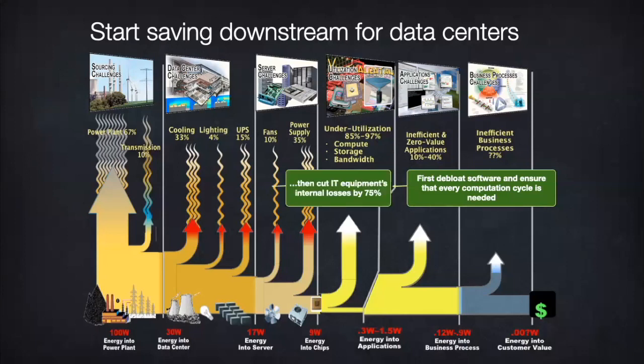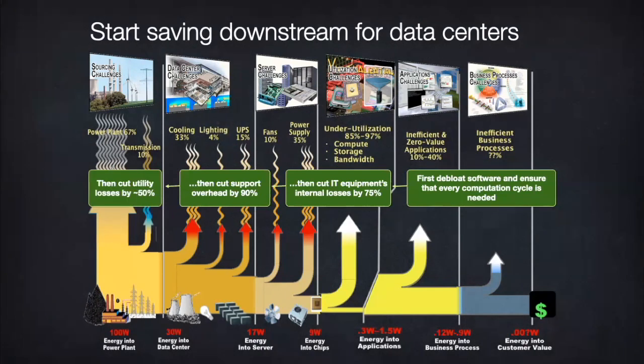Then at least quadruple the server efficiency, now even more, and the servers will need far less cooling and power supply, both of which can be done in smarter ways. We could even save half the utility losses by using fuel cell trigeneration, cheaper than the uninterruptible power supply it displaces. Now multiply these savings from downstream to upstream, and you get at least 2 orders of magnitude energy savings.